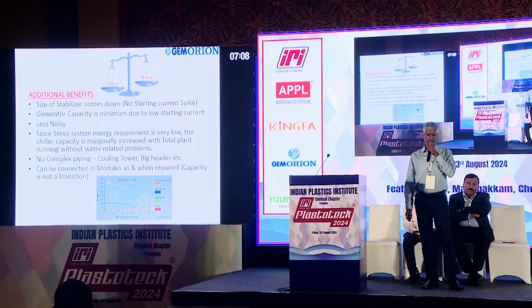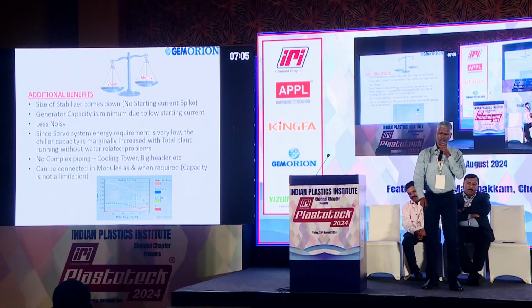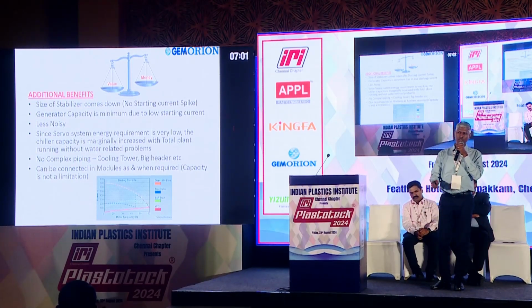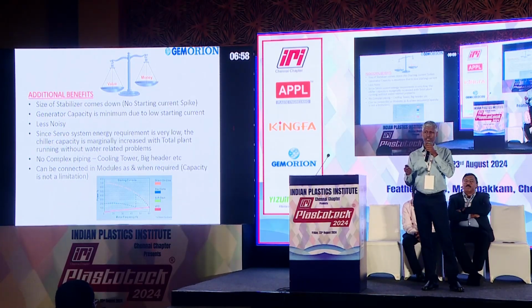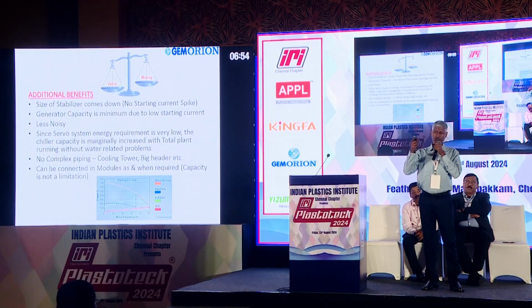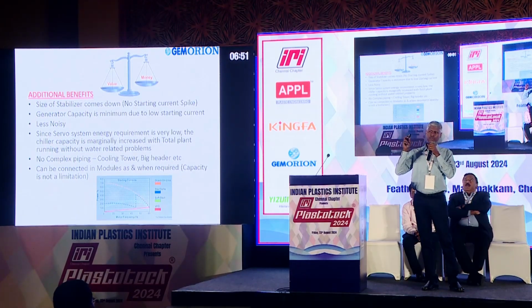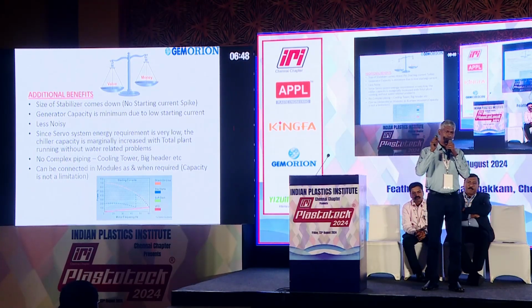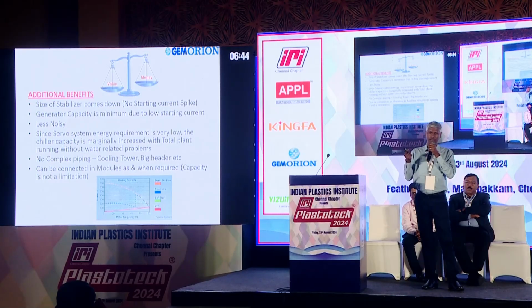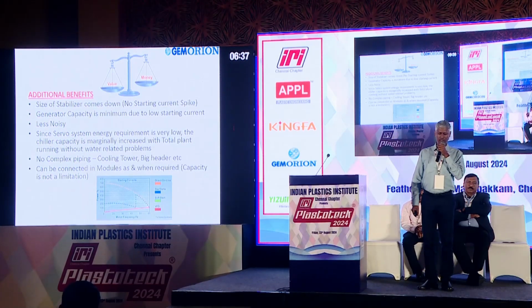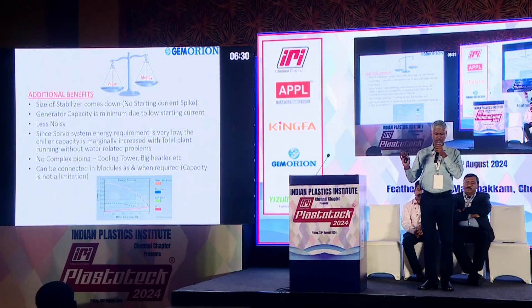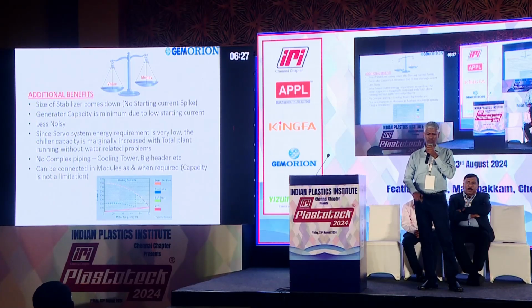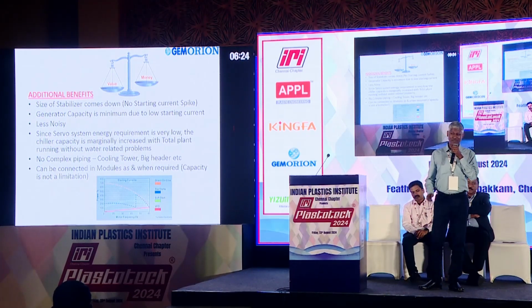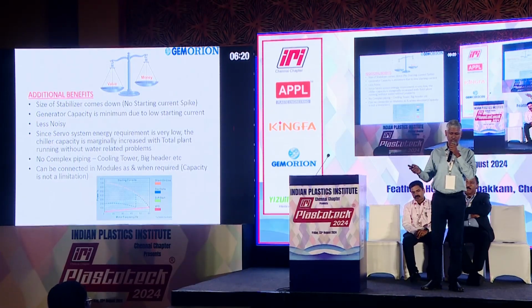Additional benefits to the customers: the size of stabilizers comes down. We say here, no starting current spike. Even at home, you can observe when your refrigerator compressor switches on, you can see or feel the light flickering. That is because when the compressor is switched on, it consumes more current. The starting current of an induction motor is quite high, about 6 to 7 times the running current. Whereas in the inverter chiller, it is quite stable. The maximum current it consumes is equal to the running current. Because of this, even for your generator, you need not go for a bulk load capacity. It is also much less noisy compared to a conventional chiller.